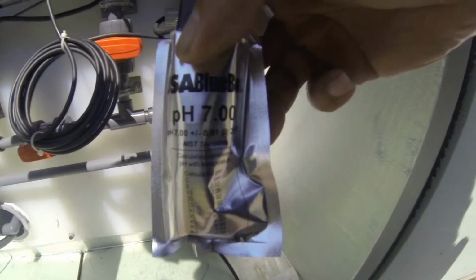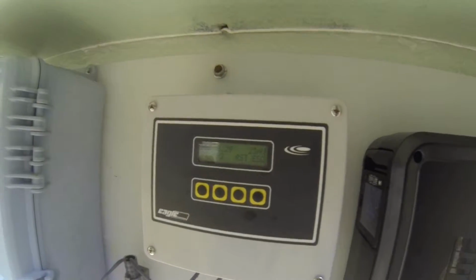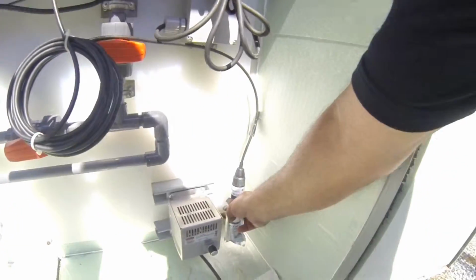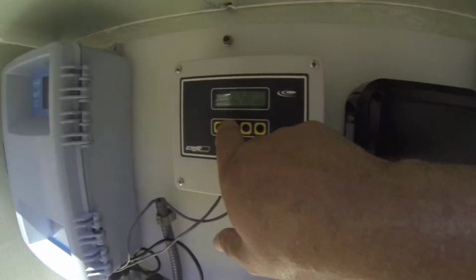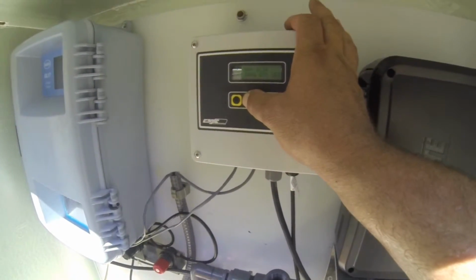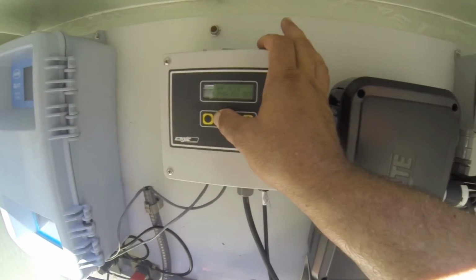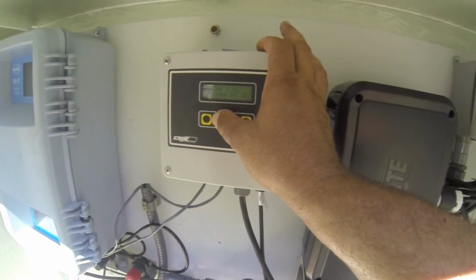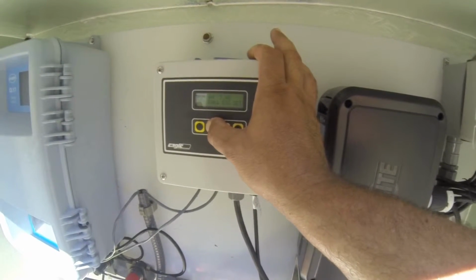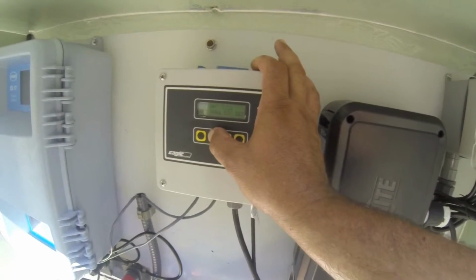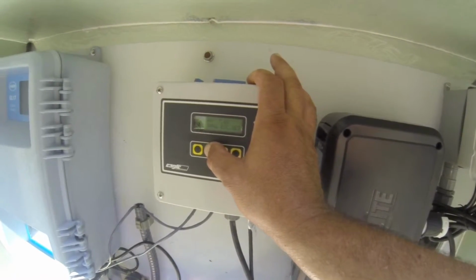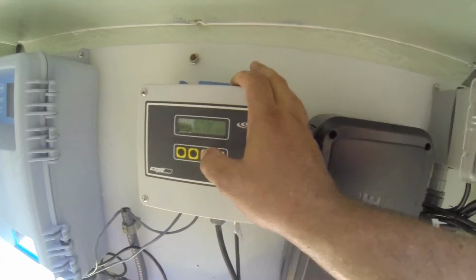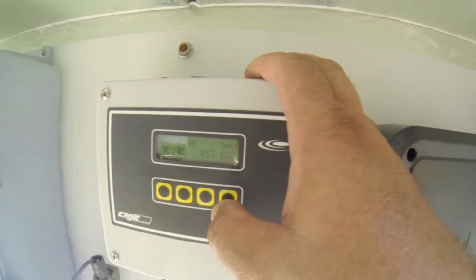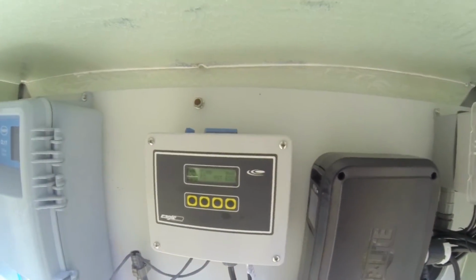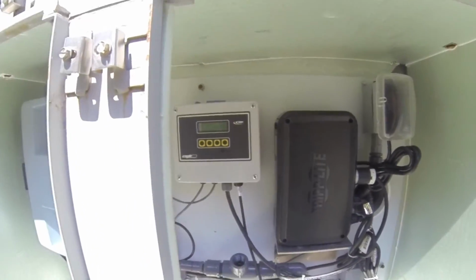Now that we're in our number 7 solution, we're going to do the same process. Only this time, we're going to set this down here and we're going to go to P2, and we're going to go down until we get to 7.00. And once we set it on that approximate value, then we hit the button that says set, and that is set as well. So now I'm going to shut the camera off.